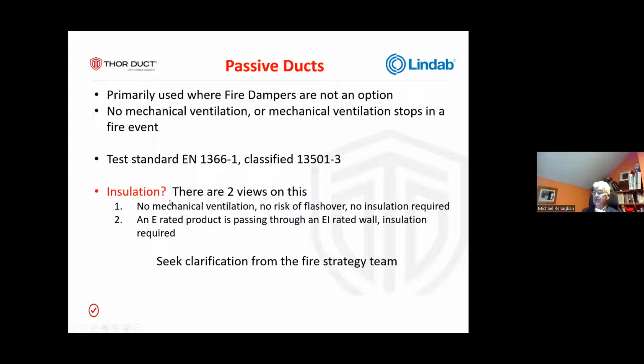The question is, do I need to insulate it? There are two views on this, and this has not been decided. And really, it should be determined first. But I know the one that most fire engineers are coming down on. The first view is that there's no mechanical ventilation, so therefore there's no movement of air, not much anyway. There's no risk of flashover, no insulation required. Okay, so what is it there for? I mean, what's its purpose?